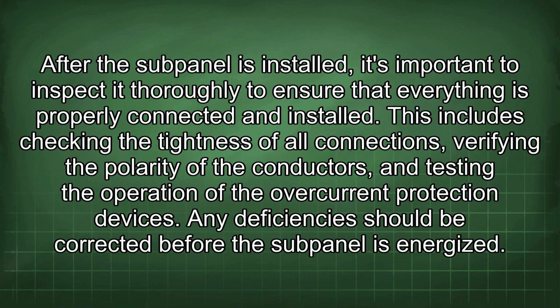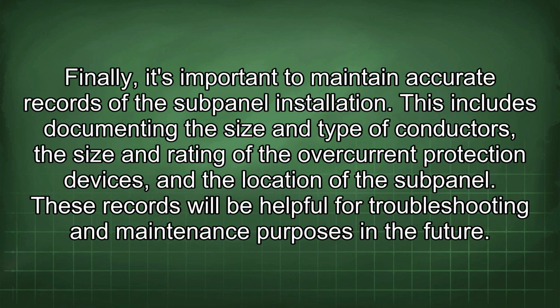After the subpanel is installed, it's important to inspect it thoroughly to ensure that everything is properly connected and installed. This includes checking the tightness of all connections, verifying the polarity of the conductors, and testing the operation of the overcurrent protection devices. Any deficiencies should be corrected before the subpanel is energized. Finally, it's important to maintain accurate records of the subpanel installation. This includes documenting the size and type of conductors, the size and rating of the overcurrent protection devices, and the location of the subpanel. These records will be helpful for troubleshooting and maintenance purposes in the future.